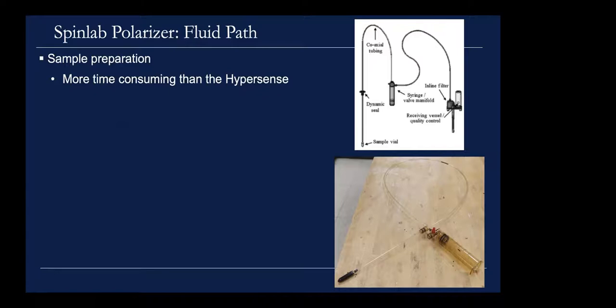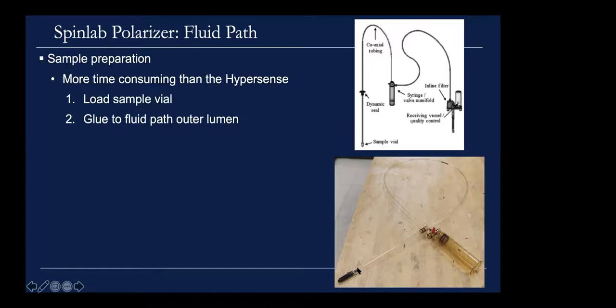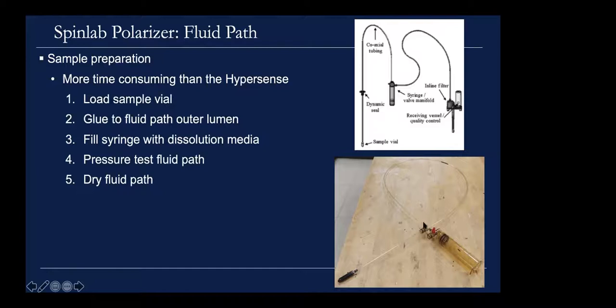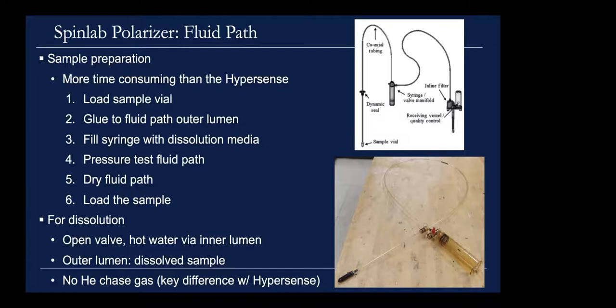SpinLab sample prep is more time-consuming than the Hypersense. With the Hypersense, you put your sample in a cup, load it on the stick, and you're done in about 30 seconds. For the SpinLab, you must load the sample in a vial, glue the vial to the plastic lumen, load dissolution media in the syringe, pressurize, perform a pressure test on the fluid path to check for blockages, dry it to remove residual moisture, then load the sample. However, because you can polarize multiple samples simultaneously, you can usually recoup that front-end prep time on the back end.